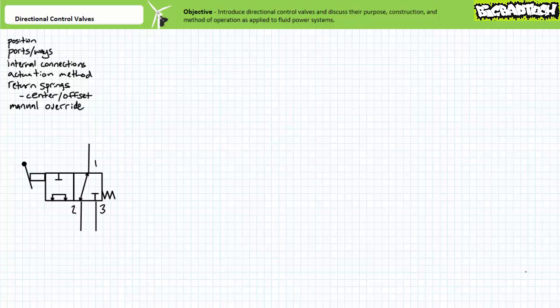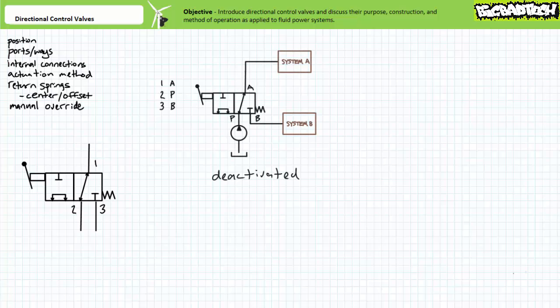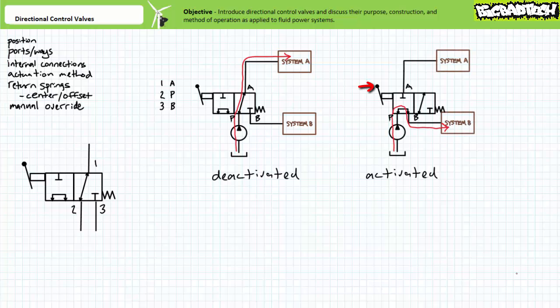Given that these arrows are bidirectional, consider a couple of creative ways this valve can be put to use. Consider a configuration making use of port two as the pressure port, port one as the input to system A, and port three as the input to system B — we have in effect created a selector valve. In the deactivated state, pressurized flow is routed to system A. In the activated state, pressurized flow is routed to system B, thus selecting which port and system receives pressurized flow.